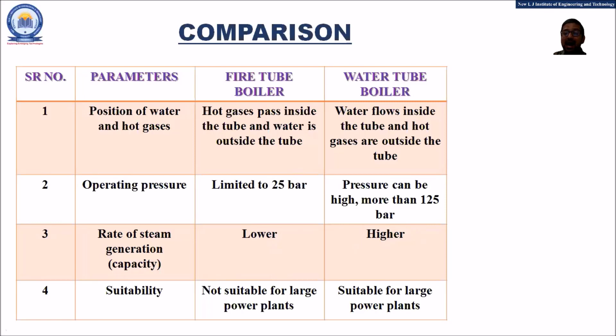Next point, the rate of steam generation or the capacity. The fire tube boiler has lower capacity, whereas the water tube boiler has higher capacity. So in the fire tube boiler, the operating pressure is less and the capacity of steam is also less. But on the contrary, for the water tube boiler, the operating pressure is higher and the rate of steam generation is also higher. Therefore, considering suitability, fire tube boilers are not suitable for large thermal power plants. But water tube boilers are perfectly suitable for large power plants.